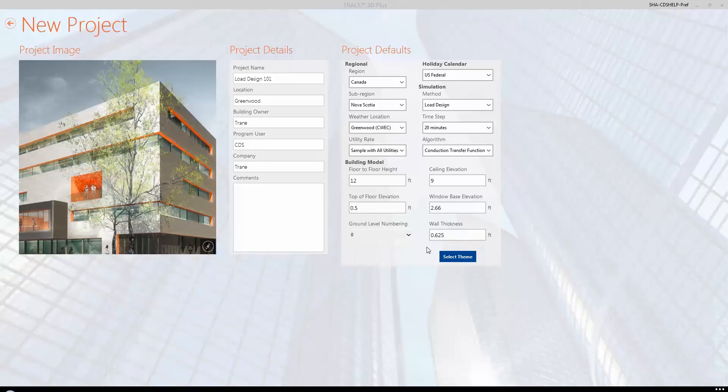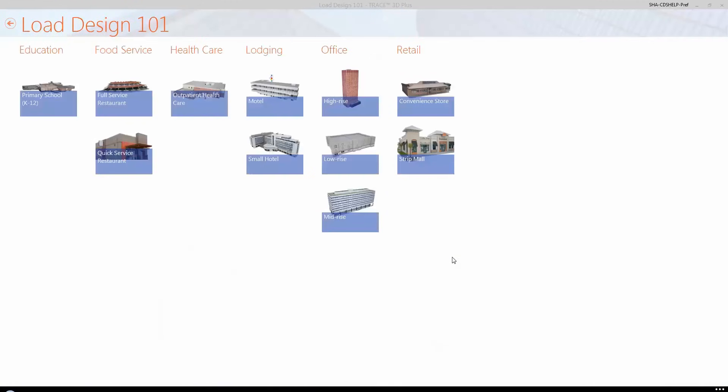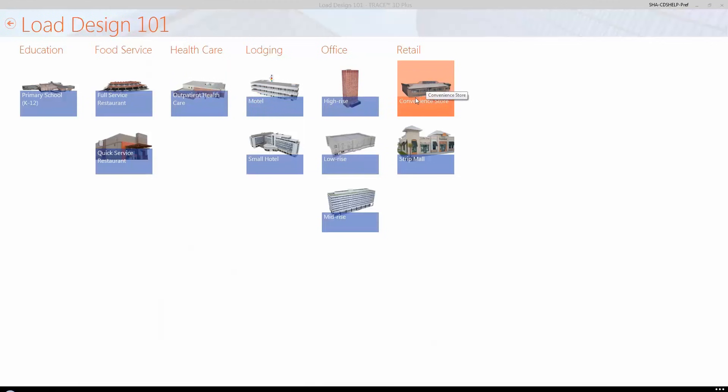After the building information is entered, we will click on the Select Theme button. Themes are essentially building types with predefined template data including construction materials, space or room types, thermostat settings, and internal and airflow loads. These themes will simplify your input process and are used to assist with facilitating mass changes across a project. Themes also provide important default data when creating new rooms in the Create Buildings section. Theme templates contain construction, room type, and zone types that reflect typical data for the building type selected, but they can be edited within the Theme section or within the Site and Buildings section of Trace. Trace 3D Plus has several themes including education, food service, health care, and many others. All of these templates can be customized, giving us a good starting point for our building.